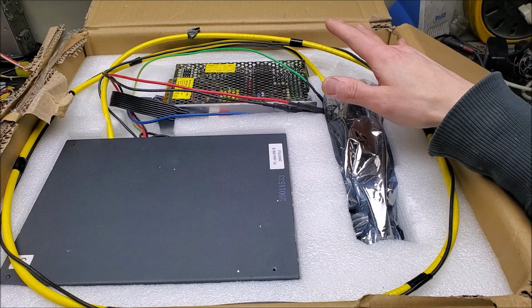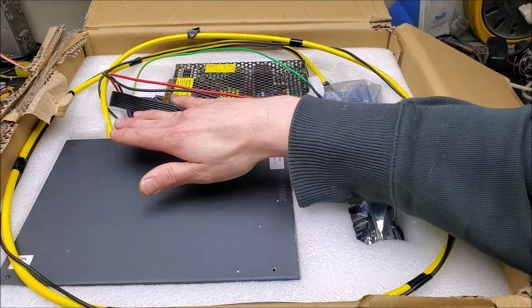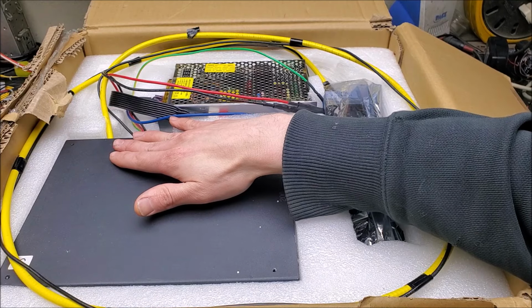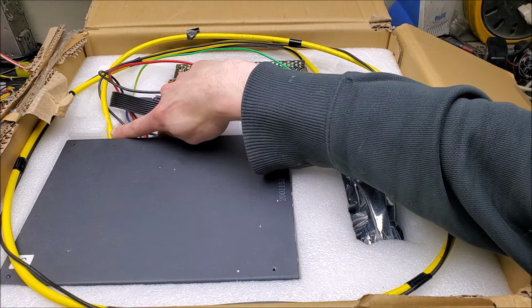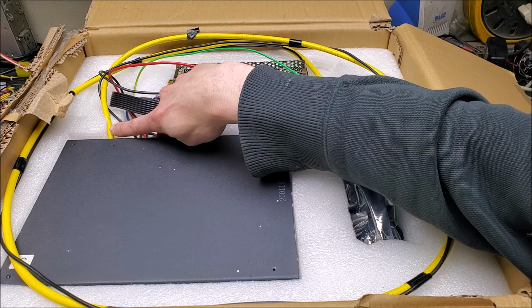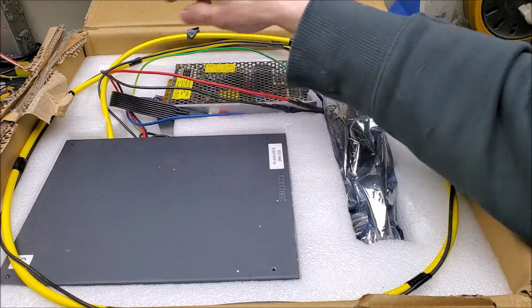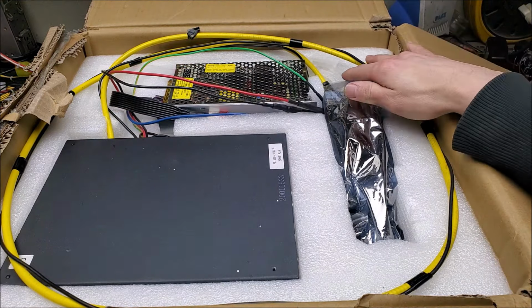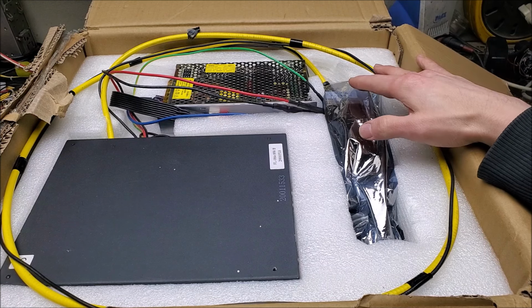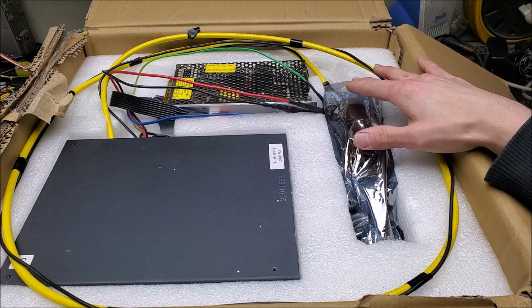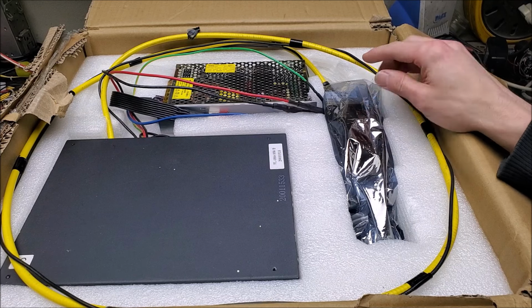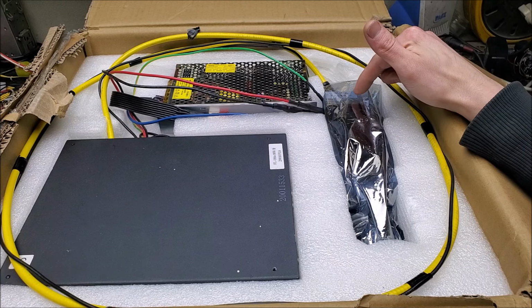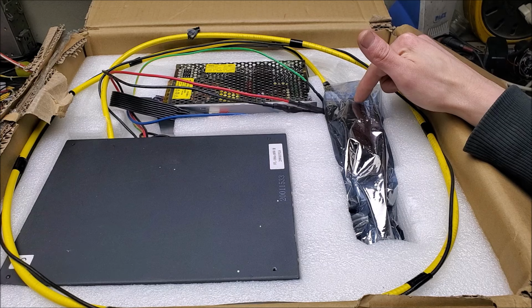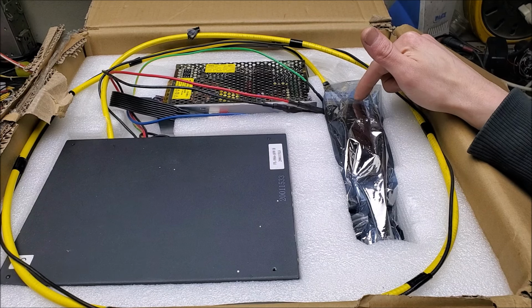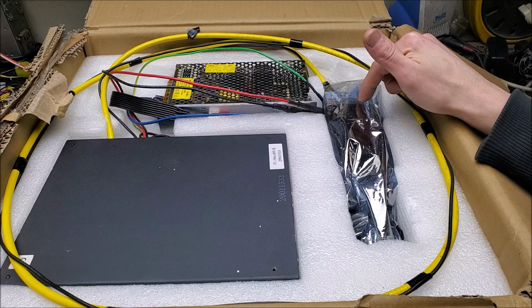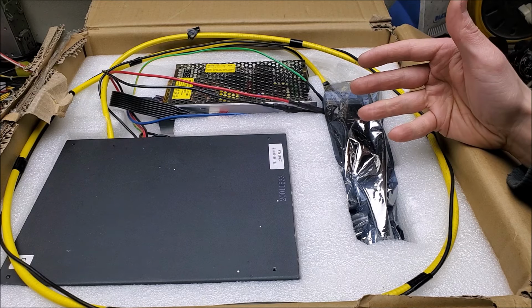Now, what I think is going on is we've got an 808 nanometer pump laser diode here, and that 808 nanometer laser light goes through this yellow fiber optic cable, and that light exits the fiber on the inside of the laser head. Since it's a pulse laser, I think we have a neodymium doped yttrium aluminum garnet, or Nd:YAG, crystal on the inside of the laser, as well as some sort of passive Q switch.